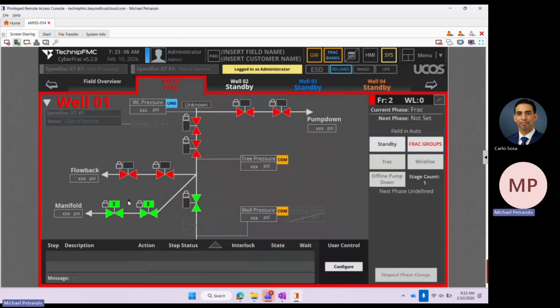Perfect example, if I have 4,000 PSI on the tree pressure, I need to have a reading on frac in order to keep me from opening these zipper valves. If I have 0 PSI here and I open these zipper valves, we're going to blow pressure right through the line. Same goes for pump down. So we make a lot of comparisons to say, what is tree pressure versus frac, or what is tree pressure versus pump down? And then if you have additional sensors, like wireline pressure and flowback, it's just an added benefit. We can get more interlocks applied at those points.